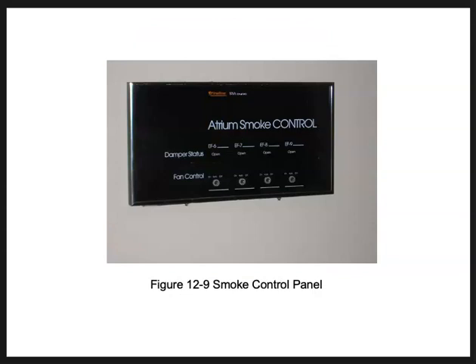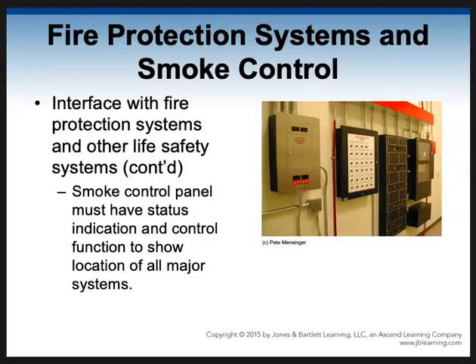The smoke control is going to be related to the fire control panel, but it's going to have its own smoke control panel as well. And they're usually in a room that looks somewhat like this. It's a big interface with, we talked about addressable systems or systems where the firefighters can talk to people on different floors, an intercom system. All of this you can see in this picture on the right. Smoke control system panel, alarm system panel, that voice system, all of these things working together. And usually they'll have a room dedicated to this. It's the fire control systems room for high-rise buildings.